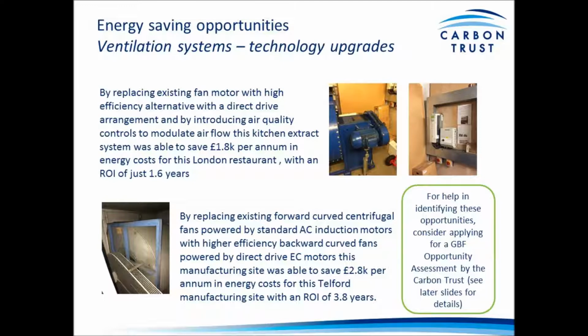The bottom example there is replacing a standard centrifugal belt and pulley fan in an air handling unit with a purpose-designed free spinning, high efficiency direct drive, electrically commutated or EC plug fan, which saved around 30% of the fan energy costs. In this example case, the manufacturing site in Telford was able to save £2,800 per annum with a return on investment of 3.8 years.